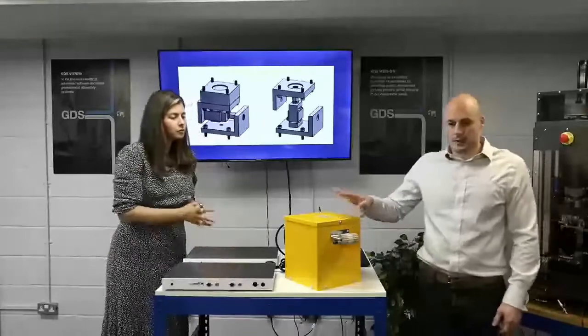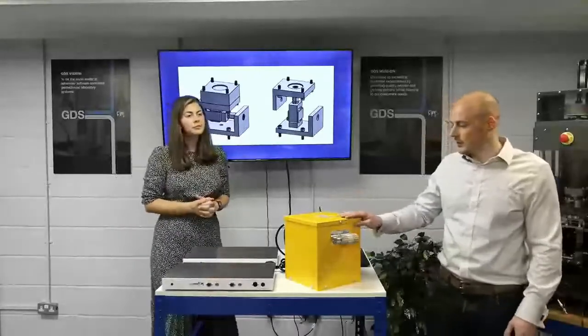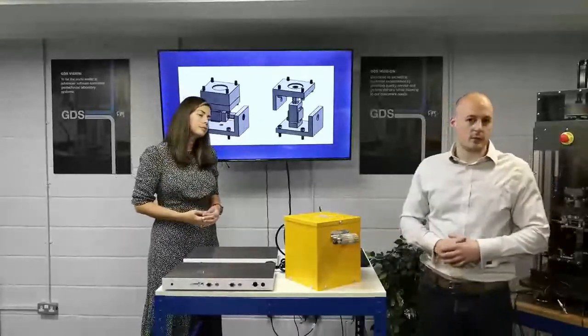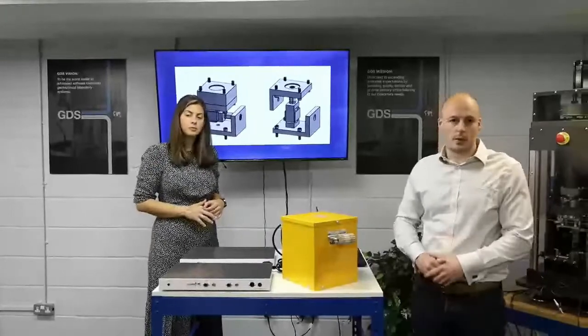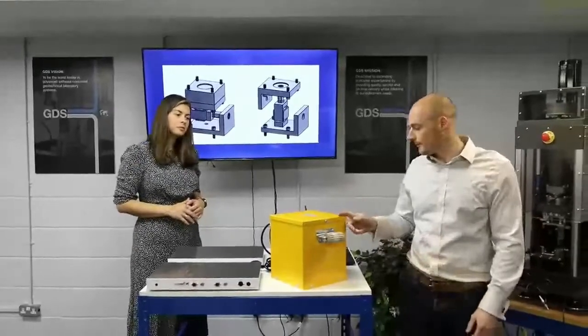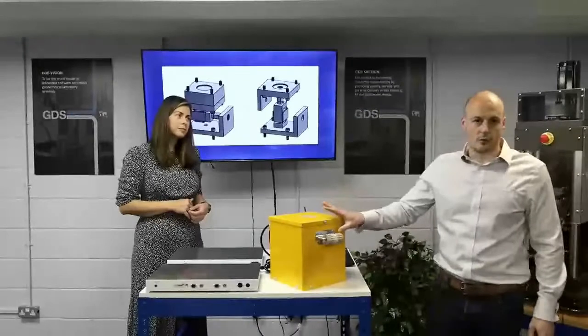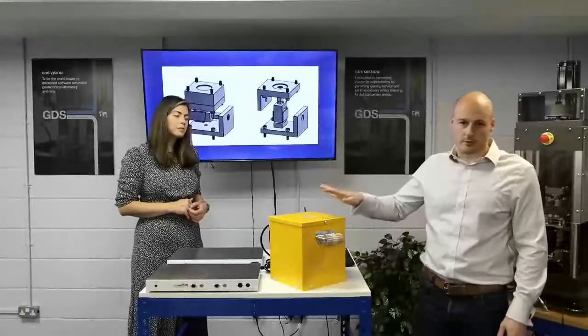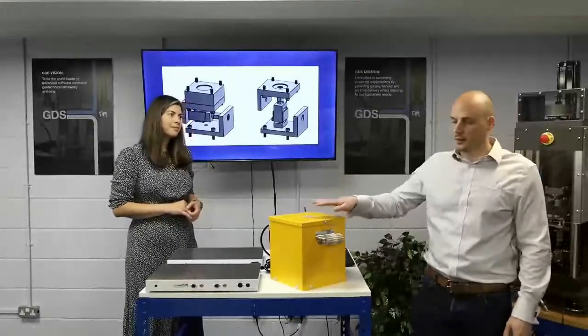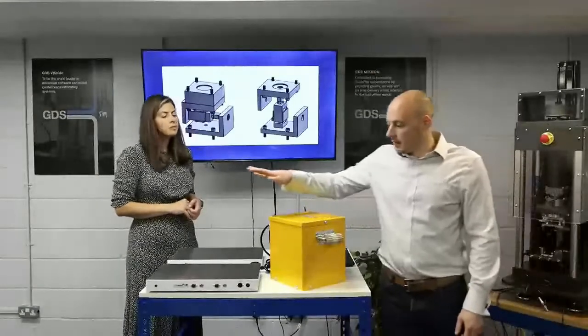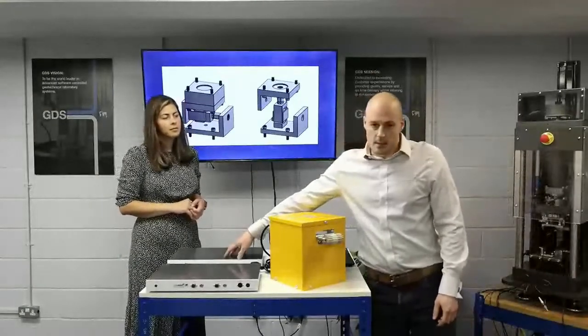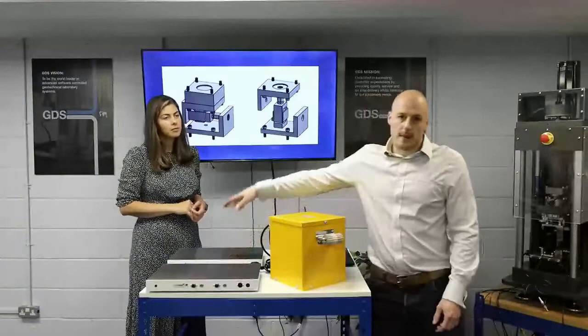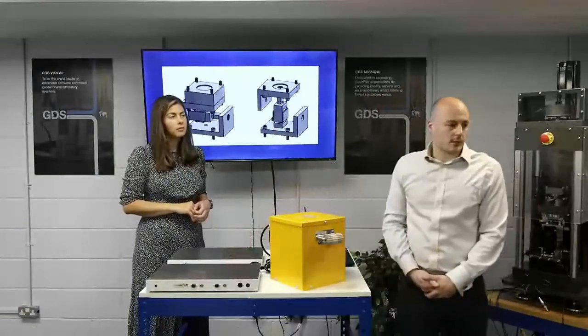It has logging channels, 24-bit acquisition, and uses a CAN bus connection. We provide the system with a single phase isolating transformer like this one, available as 240 to 240, or a step up from 120 volt to 240 volt. This reduces the inrush current, and we can run all the electrical devices through it to create a common ground. The LVDT box and the control box both come in dual voltage, 120 to 240.